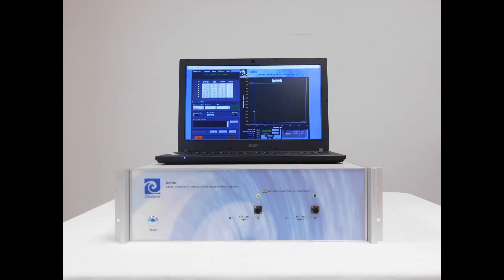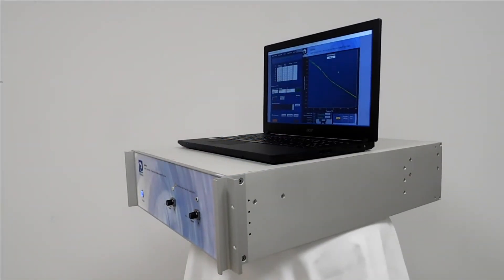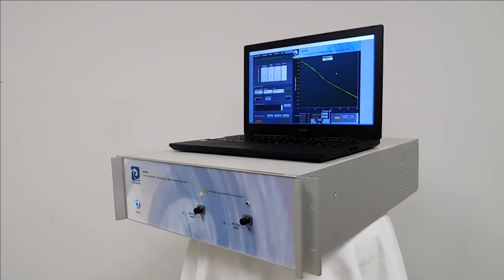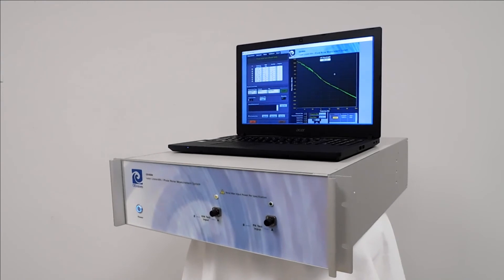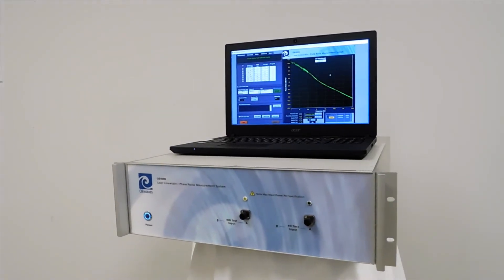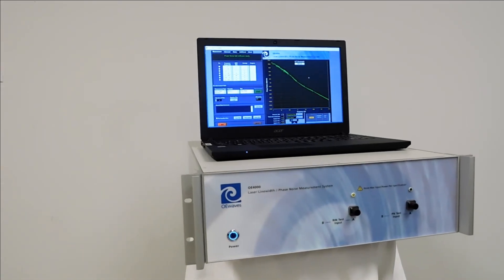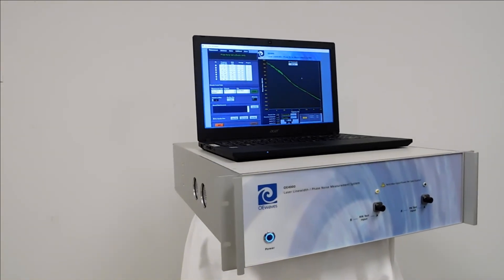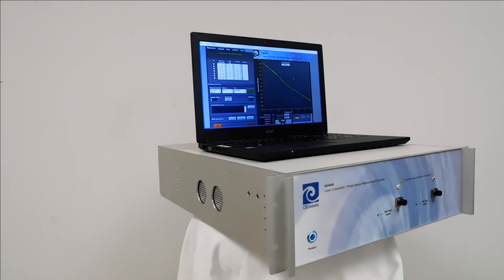Next, we will show a demo of the system measuring laser noise. The demo consists of the analyzer system and the PC, shown from different angles around the unit. The two input ports for this specific unit are the FC/APC fiber connectors — one for phase noise and the other for RIN measurements. The GUI with a phase noise plot is shown on the computer screen.